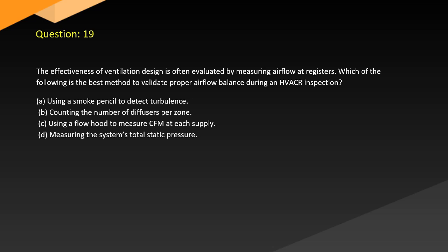Question 19. The effectiveness of ventilation design is often evaluated by measuring airflow at registers. Which of the following is the best method to validate proper airflow balance during an HVACR inspection? A. Using a smoke pencil to detect turbulence. B. Counting the number of diffusers per zone. C. Using a flow hood to measure CFM at each supply. D. Measuring the system's total static pressure.